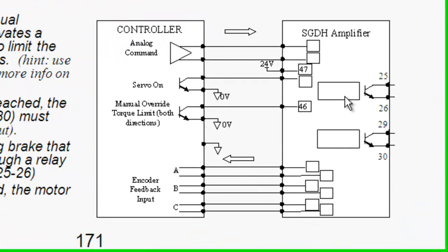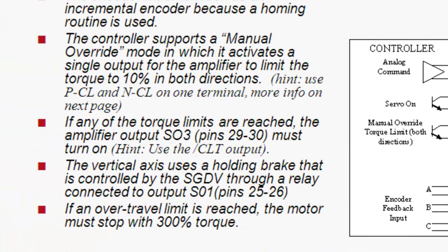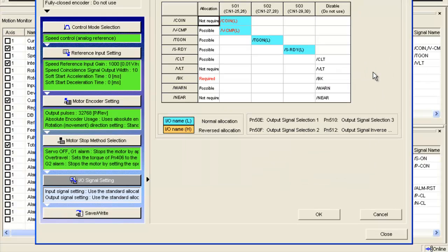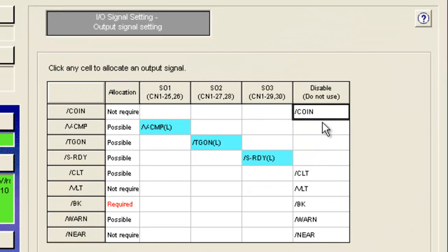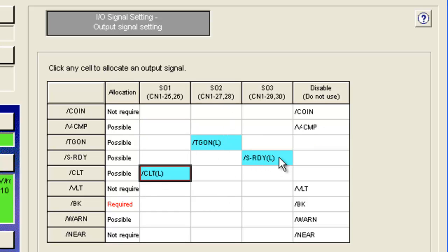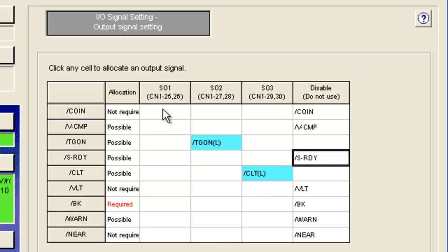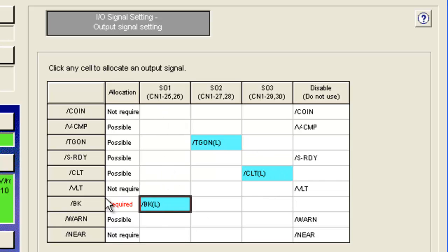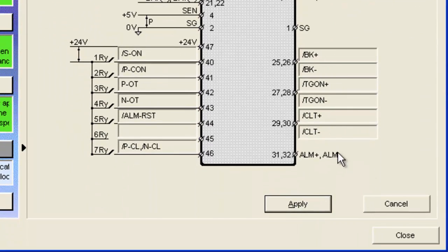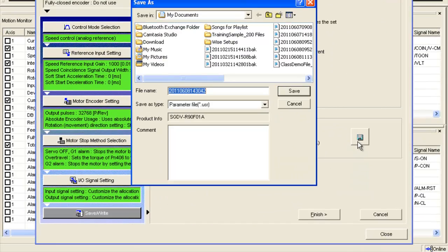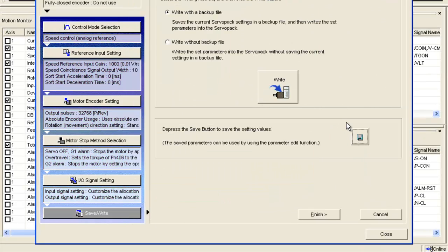In the amplifier I have two outputs specified: output one is the holding brake relay, and output three is the CLT (current limit or torque limit) output. In the wizard I'll go to the output signal setting. Output one should have the brake, and output three should have the current limit output. I can confirm this in the pictorial wiring diagram. I'll hit apply, then save this parameter file called 'speed mode'.